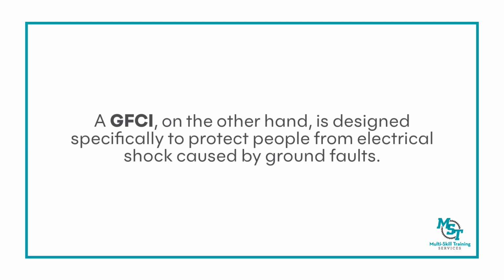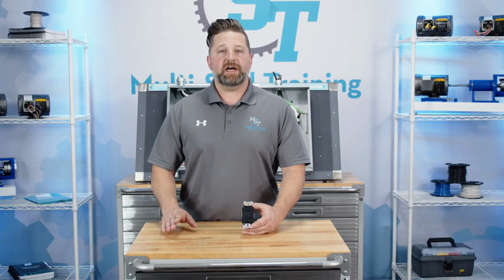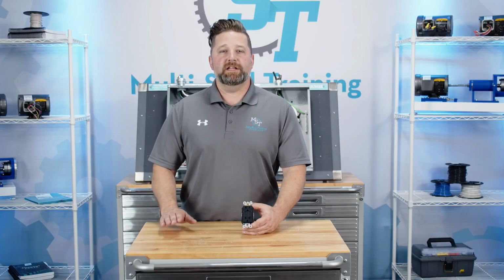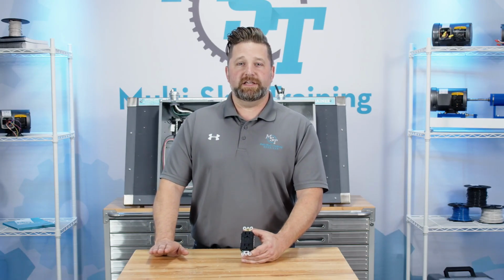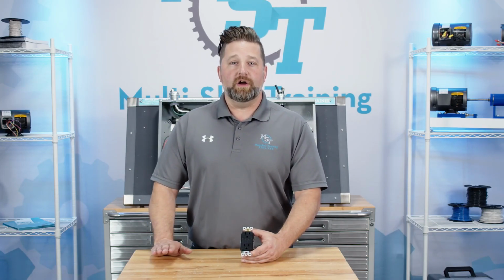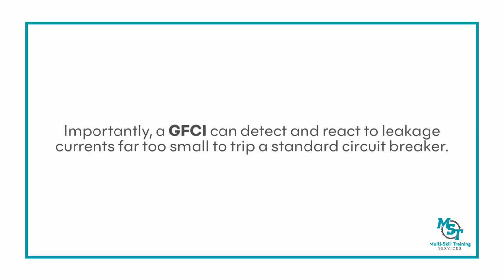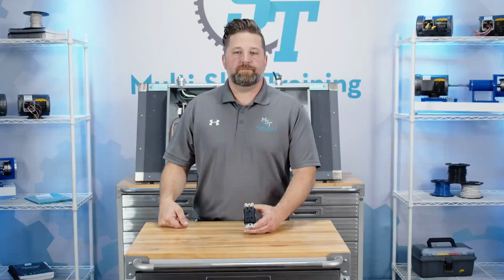A GFCI, on the other hand, is designed specifically to protect people from electrical shock caused by ground faults. A GFCI monitors the flow of electricity, leaving on the hot wire and returning on the neutral wire. If there is even a slight imbalance, indicating current is leaking to ground through a person or other unintended path, the GFCI trips almost instantly to prevent injury. Importantly, a GFCI can detect and react to leakage currents far too small to trip a standard circuit breaker.